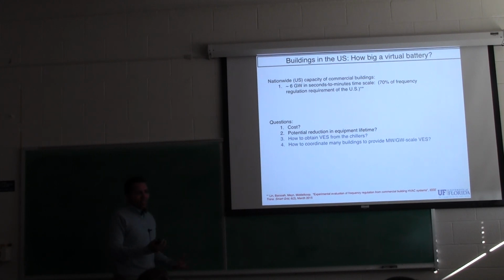The fans are only like 20% or so. Chillers are like 70% probably. The cooling tower fans are another 10-15% of the electricity, and the pumps are like 2 to 5%.